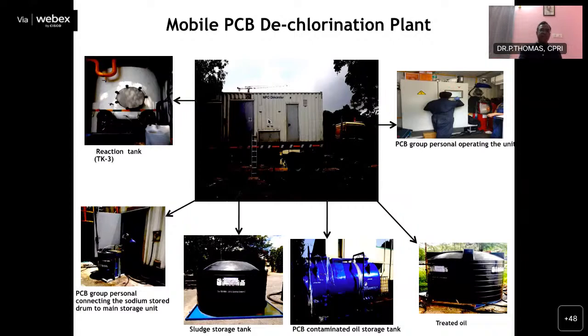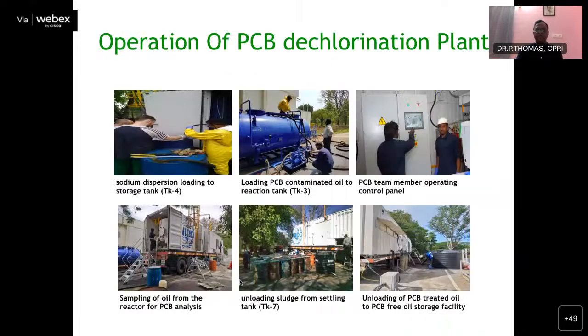Before and after the reaction we test the PCB contamination level. We may start with 500 ppm, and after the reaction check what the ppm is. We found the reaction completes in about 1 to 2 hours, and when we check the oil afterward, all PCBs are removed to less than 2 ppm. After this, we remove it as treated oil. The black portions you see here show how all of this is done.